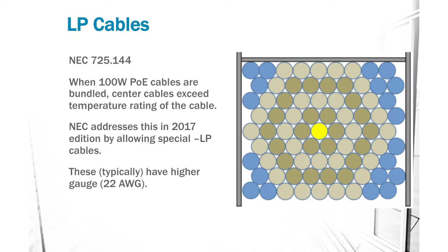But as soon as you put that PoE application on it and you're driving power down it, that's where it rises to the level of a Class 2 cable, which is governed by the NEC Chapter 725. As you alluded to earlier, it has to do with the heat, especially if you bundle cables together. So before the 2017 edition of the NEC, it gets updated every 3 years, the NEC anticipated some of these higher power PoE applications, specifically for lighting and camera applications.